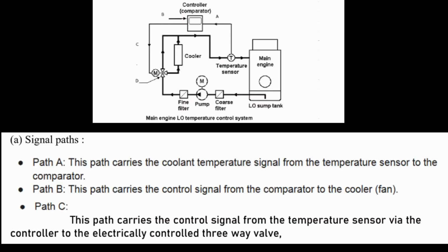A. Signal paths. Path A. This path carries the coolant temperature signal from the temperature sensor to the comparator. Path B. This path carries the control signal from the comparator to the cooler fan. Path C. This path carries the control signal from the temperature sensor via the controller to the electrically controlled 3-way valve.